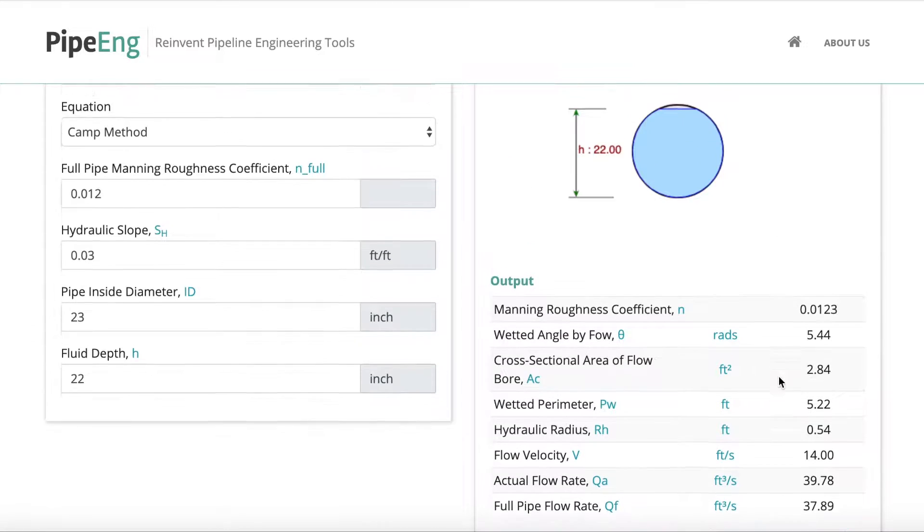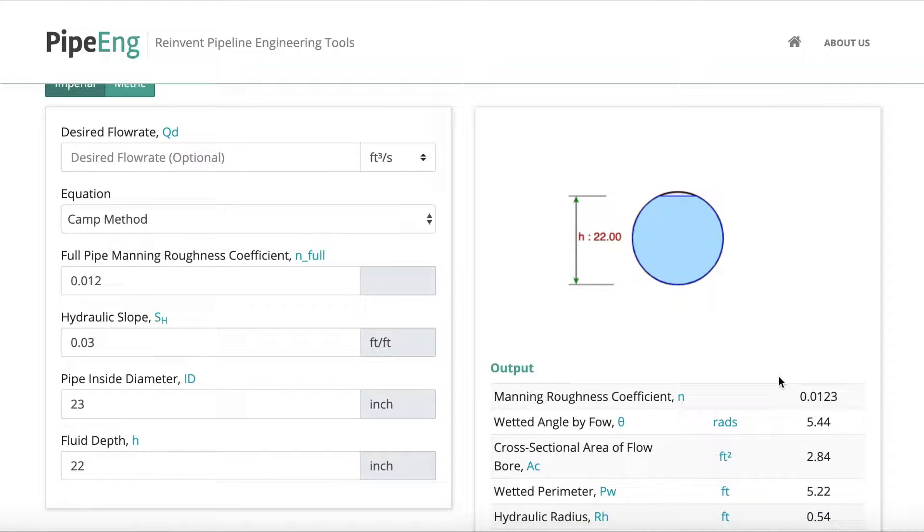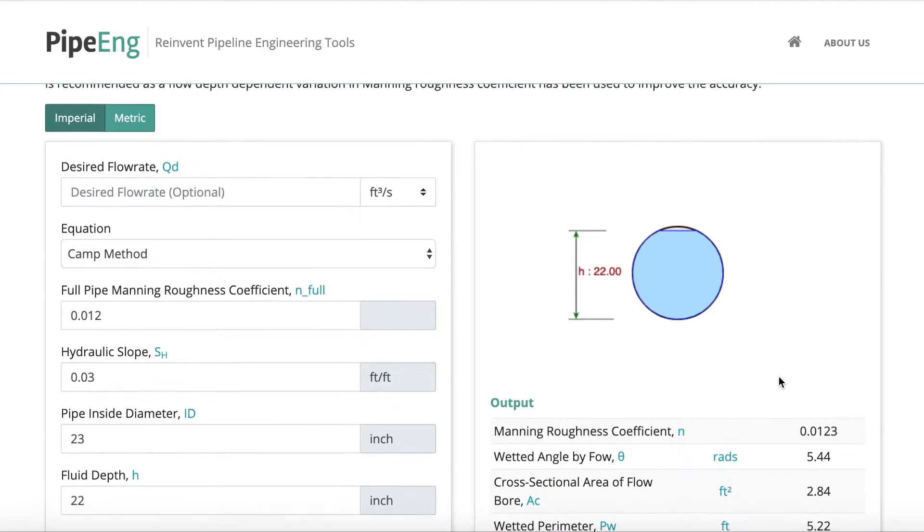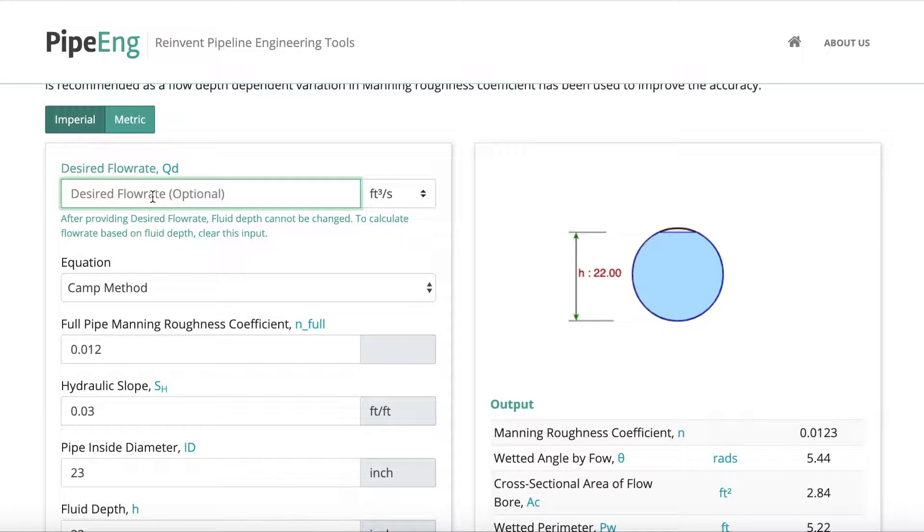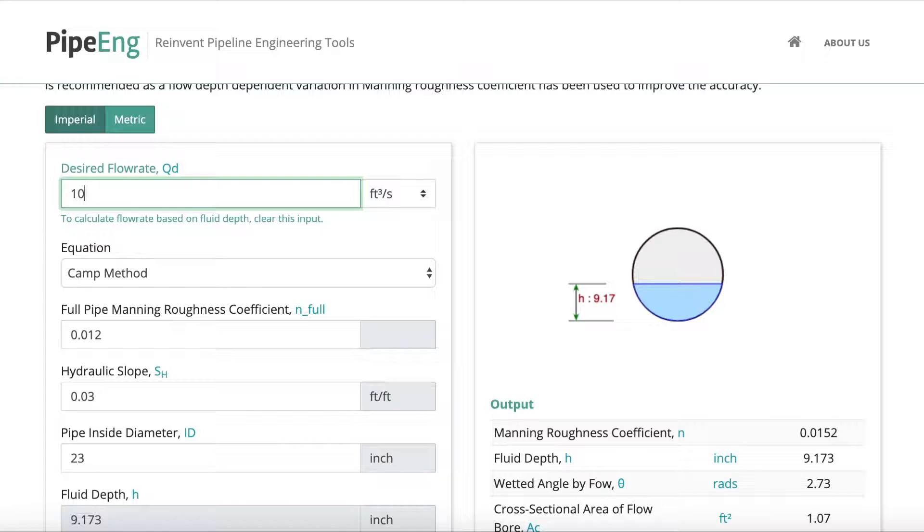Okay, so let's take a look at another scenario where you know the design flow rate, you don't have a line size yet, you know the slope available to install this open channel pipeline. And then you can use the design flow rate input here. Let's say you want to design this pipeline to 10 cubic feet per second.